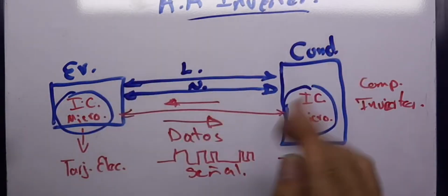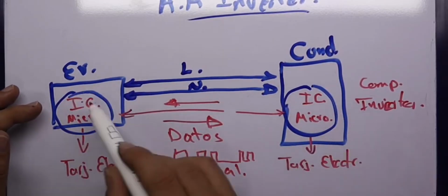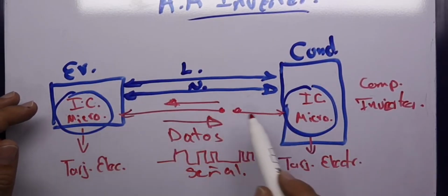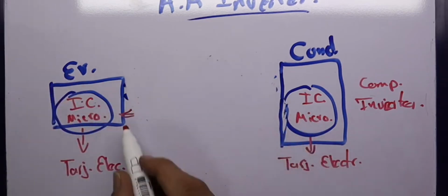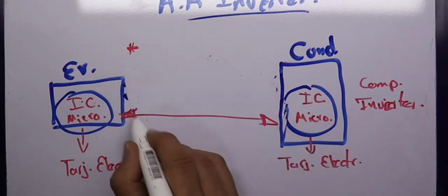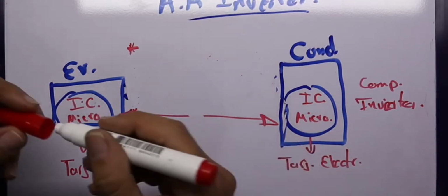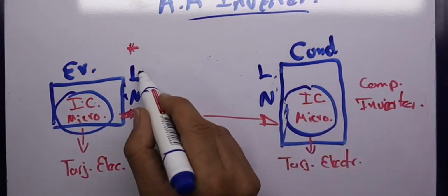Here what can happen? An intercommunication error. It could be that the intercommunication cable is cut. Yes, that cable that you are going to see now, I'm going to show you. If it is cut, there is no signal transfer. Therefore, it is going to mark the error CH5. Yes. That is to say, there we have the first error, or the first fault, that could be causing that error CH5.